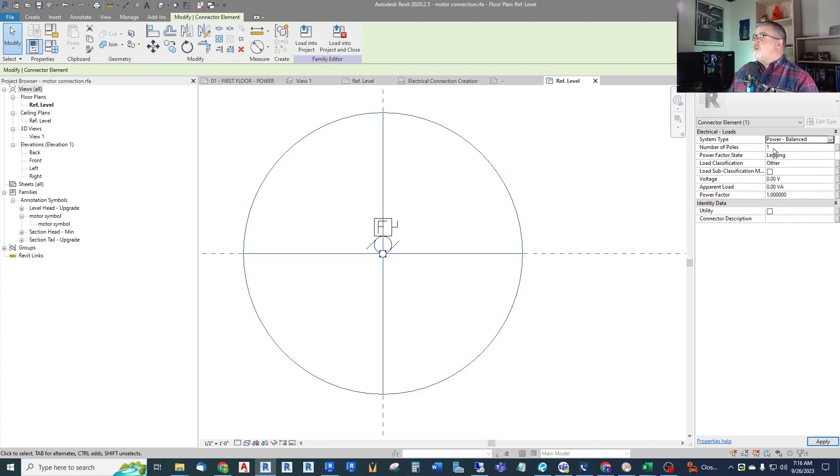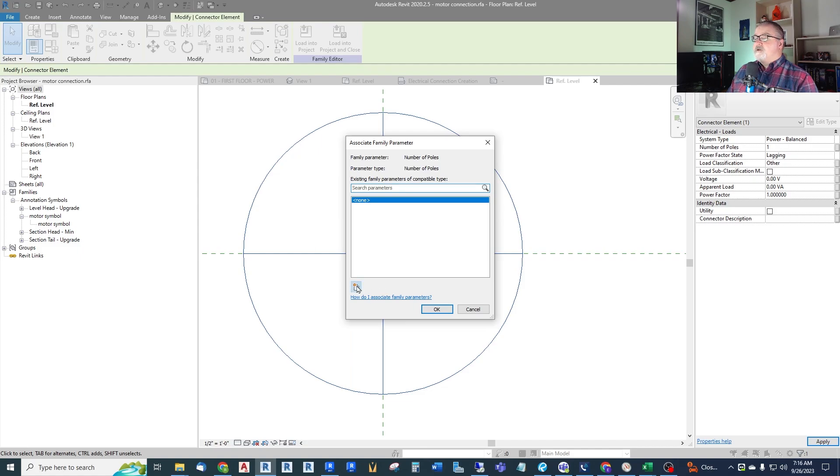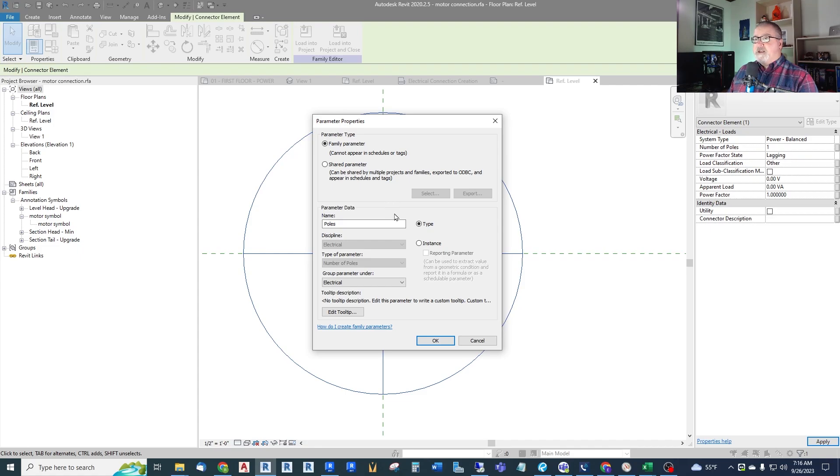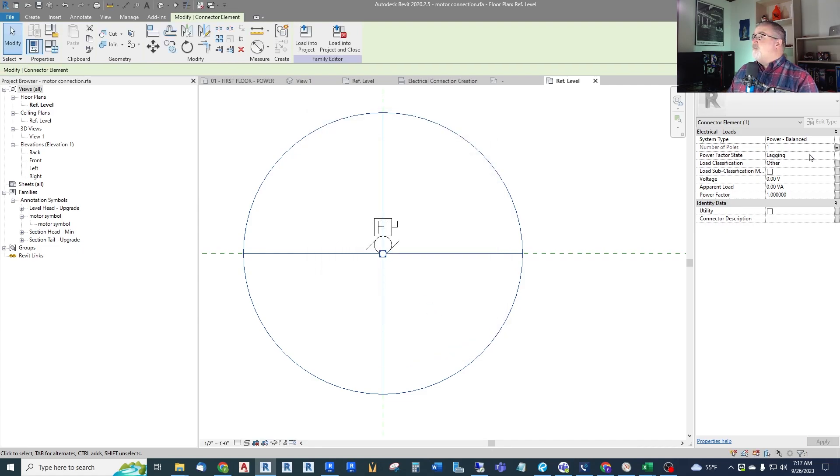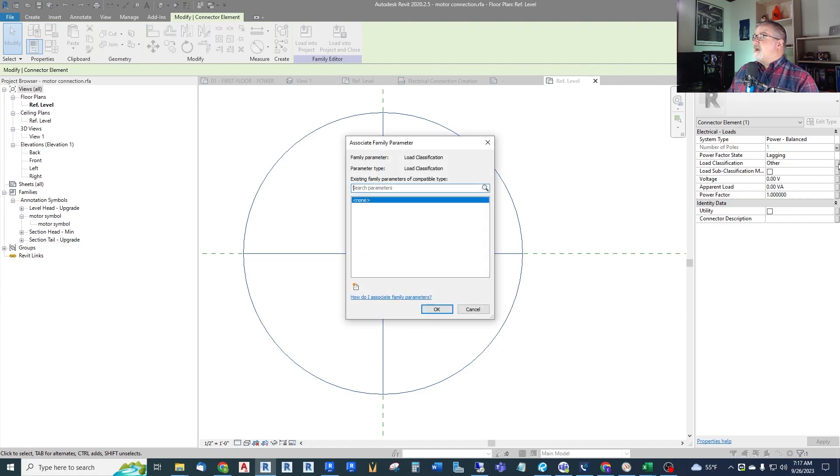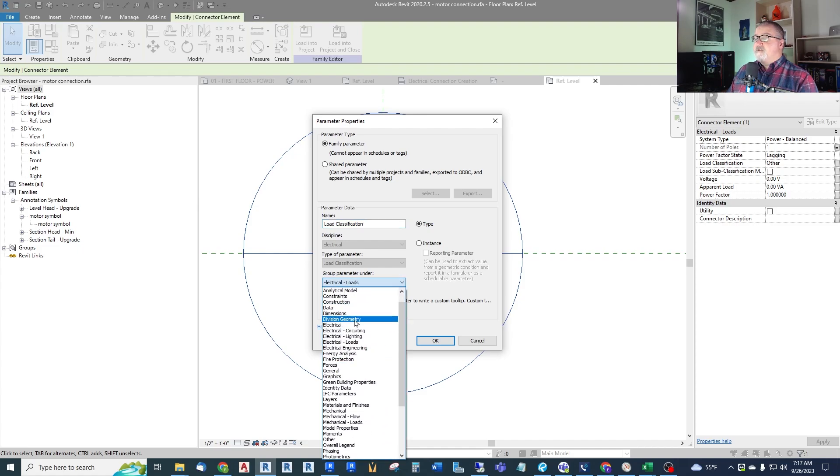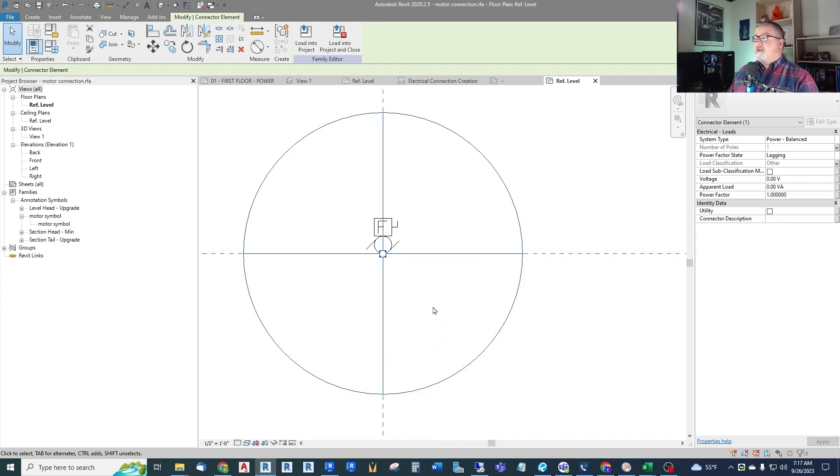Number of poles. We want this to be a family parameter that we can get to in our actual model. So again we're going to map this number of poles to a family parameter called poles which we need to create. It knows that we are looking for a number of poles type of parameter because we selected it first. So let's create that. Let's just call it poles. It knows it's electrical. It knows it's a number of poles. And we want to list these all under electrical. Now this will be a type parameter because we want to create a separate type for each motor connection that has a defined set of parameters. So okay there. And then lagging we'll just leave. Load classification. We want to be able to control that because we may want to change it to an HVAC load, a plumbing load, or an elevator load. Let's create this parameter and let us call it load classification. Another type variable. Let's put this under electrical so that it sorts together.